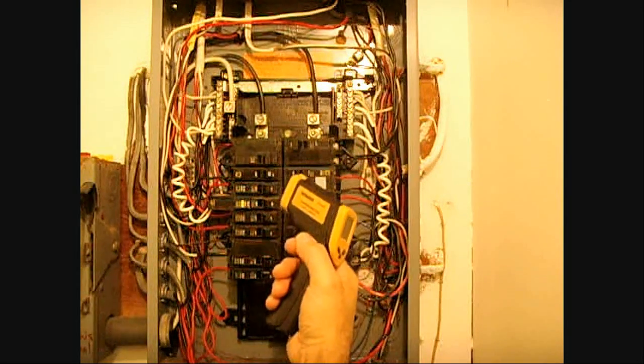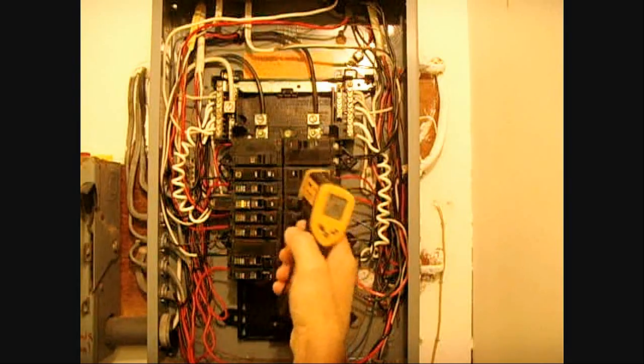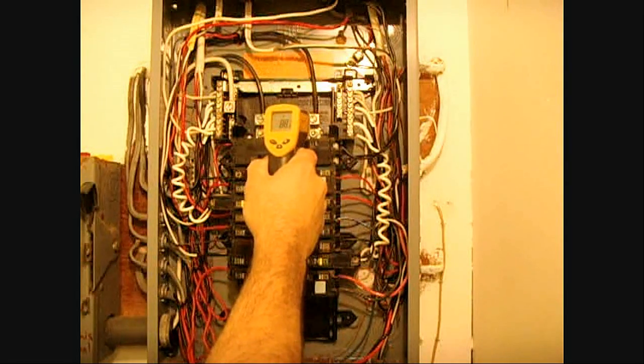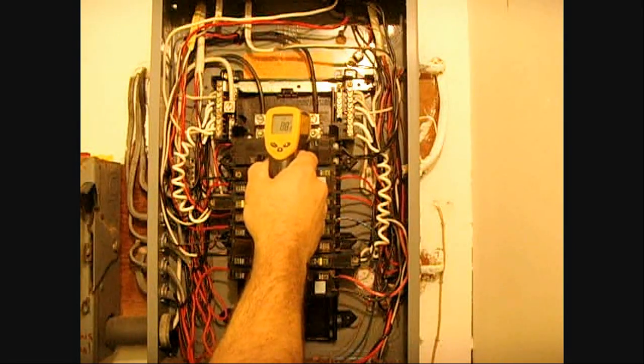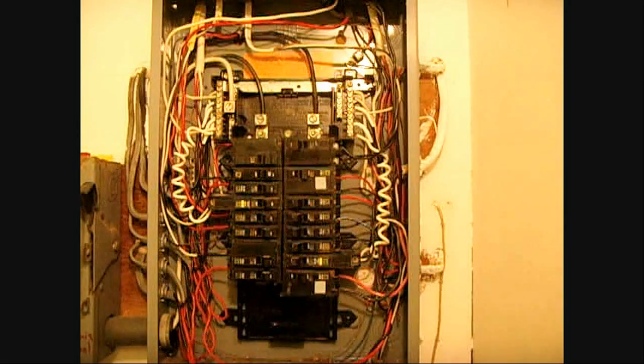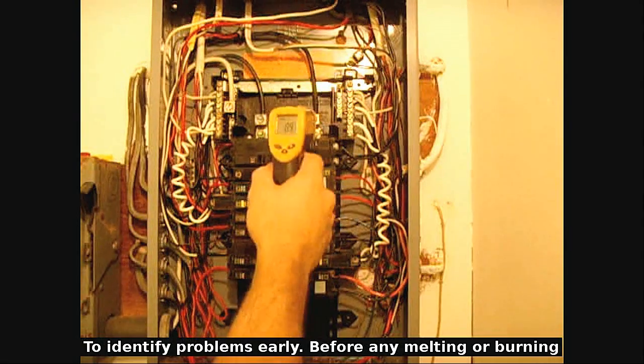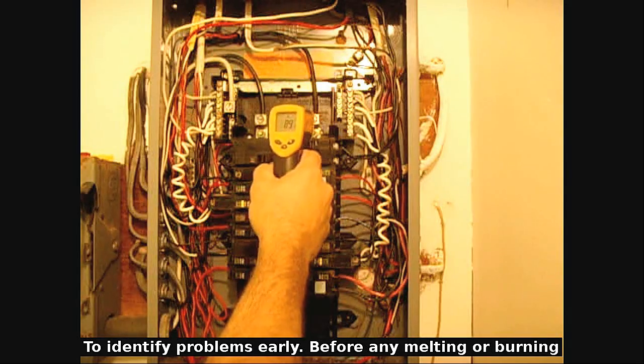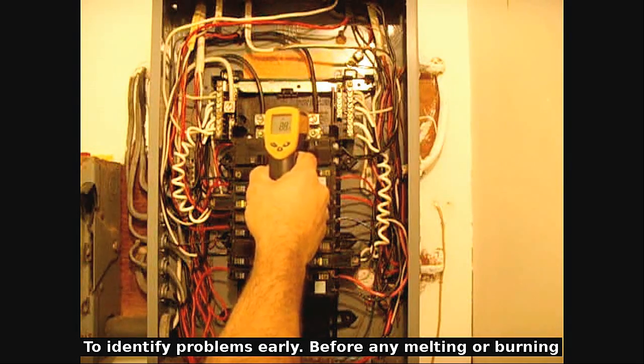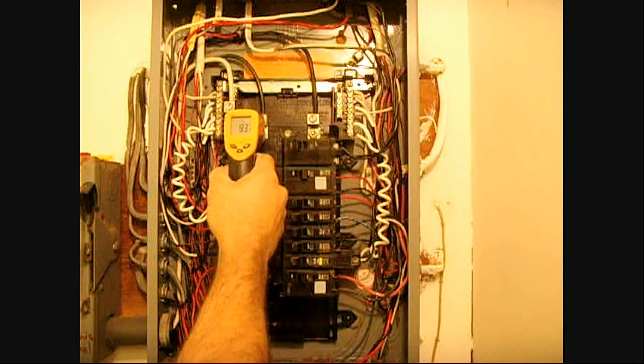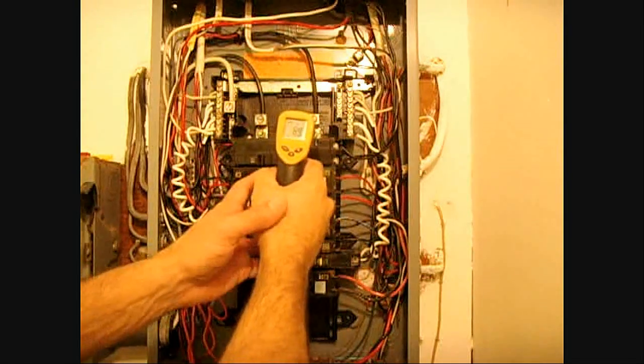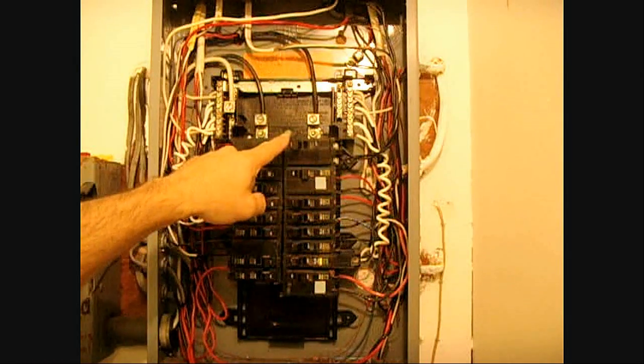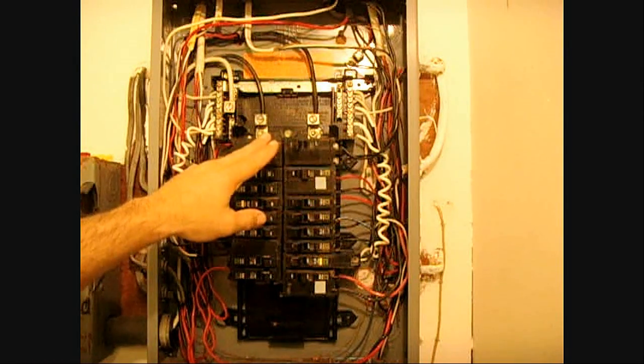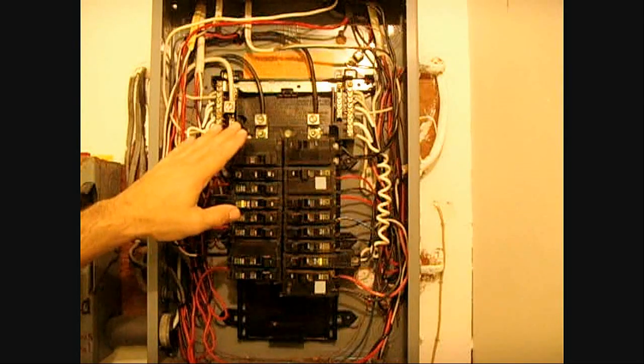Now the reason why I like this infrared thermometer is because I could take a look at connections while the power's on to see if they're generating any heat due to high resistance connections or corrosion. So I would point this at this lug at close range within a few inches. It's 89. And it's around 89 as well. If one of these came out at like 100 or 110, you're going to know that this connection here should be unscrewed and definitely cleaned and put back together.